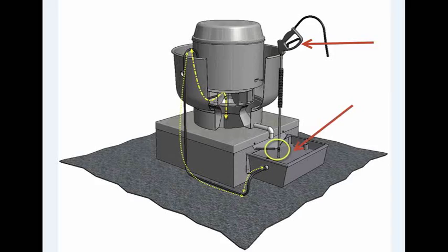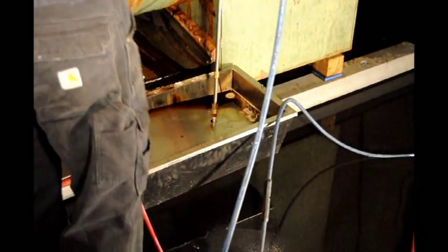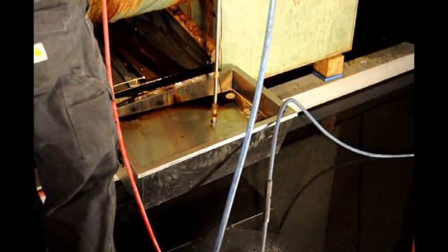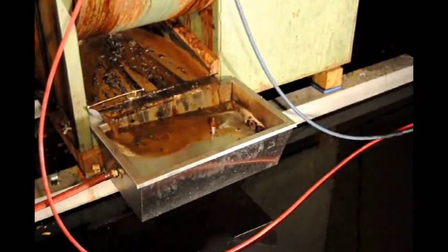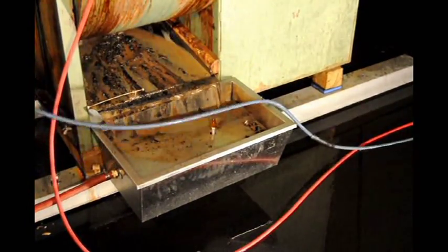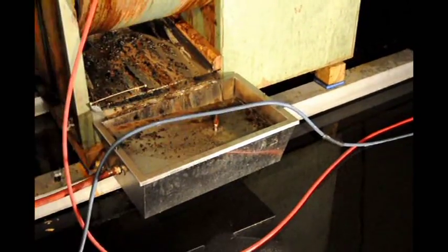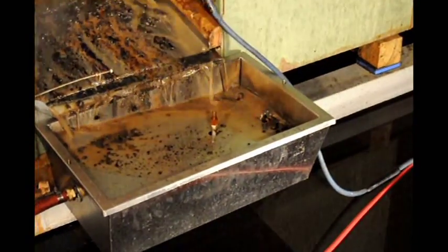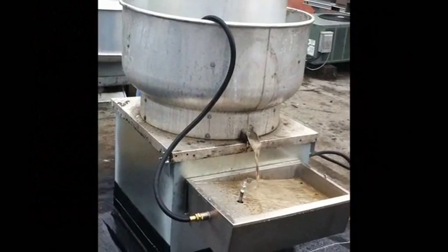Now, when the vent cleaner cleans the fan, he attaches a hose, charges the interceptor, waits for a siphon, and begins his cleaning process. As he does this, all the wastewater is now directed to a desired location, usually via duct, or to a truck, or directly to the sanitary sewer. This, by the way, saves a ton of time and effort since there is no major cleanup on the roof.